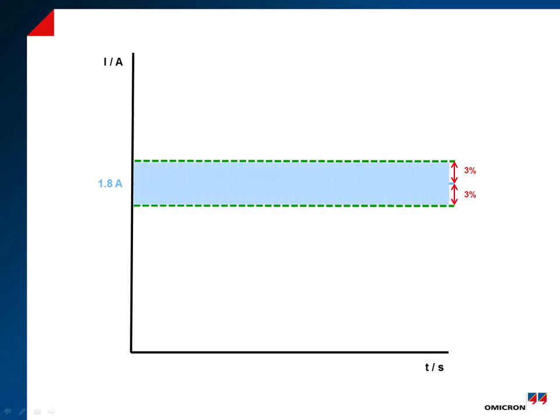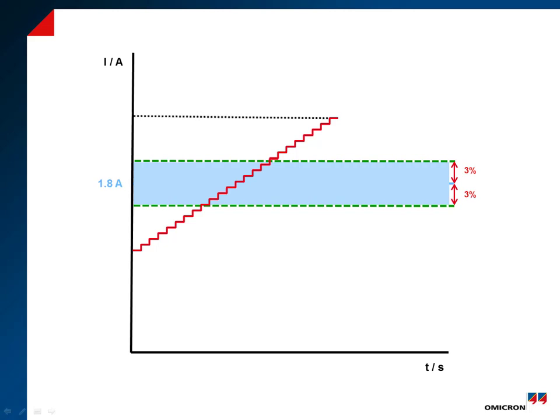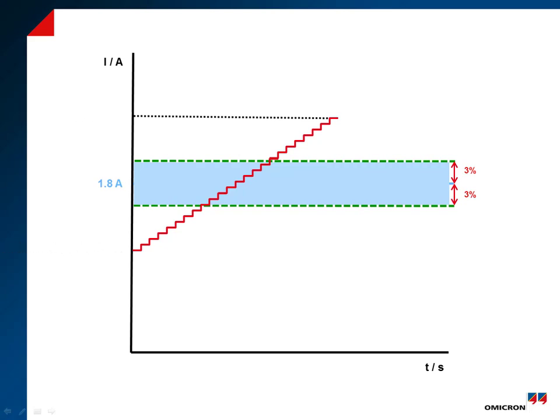Now it is time to define the start and end values of the ramp. You are free to choose any value as long as you ensure that the ramp will cross the entire tolerance band. However, just to give you an easy rule to follow, our advice is to start at 0.8 times and end at 1.2 times the nominal value. The calculated values are 1.44 amps and 2.16 amps.